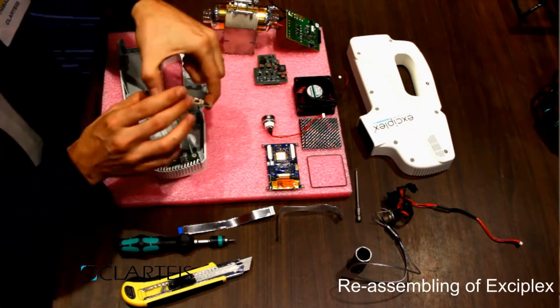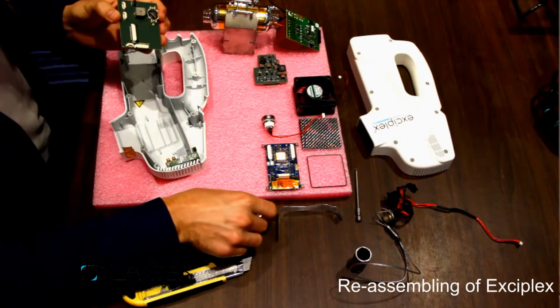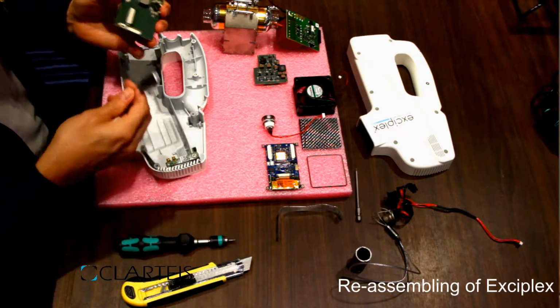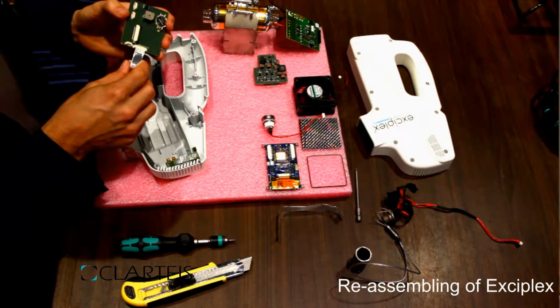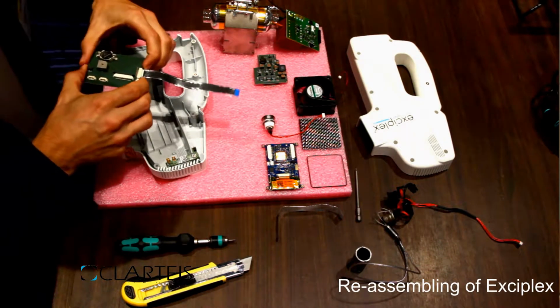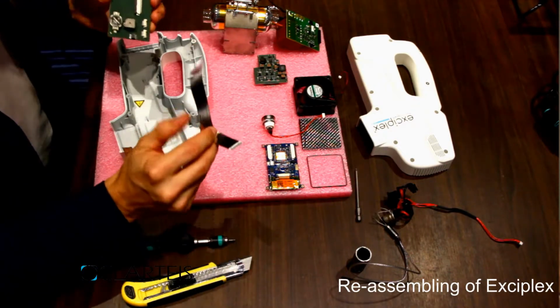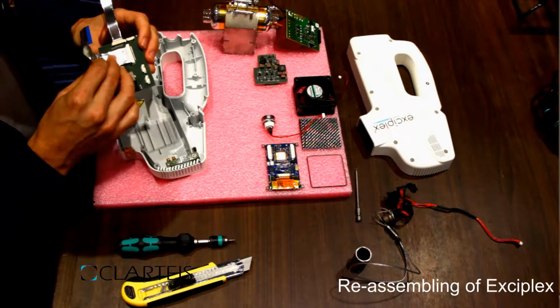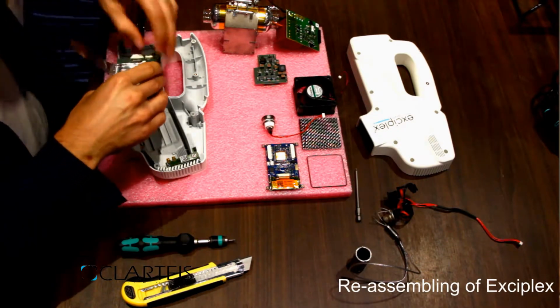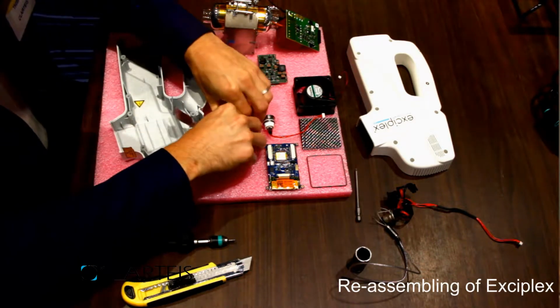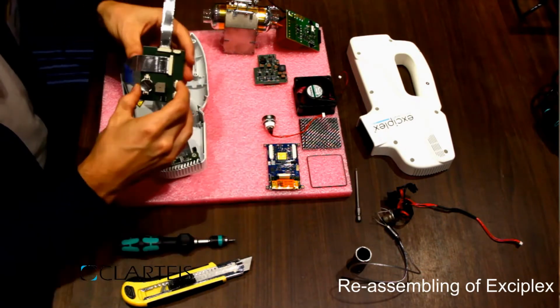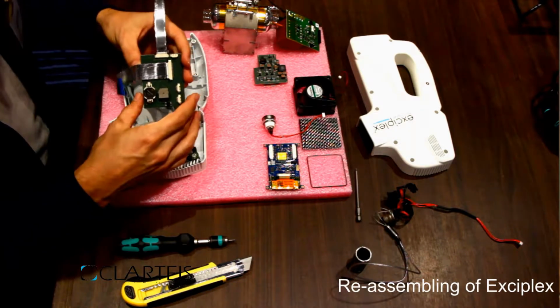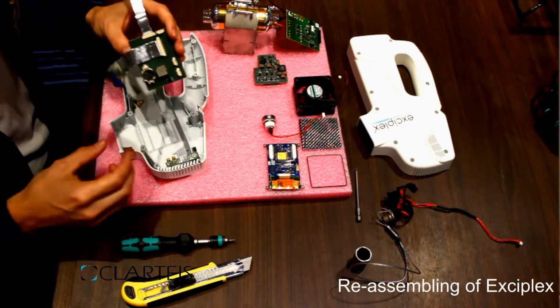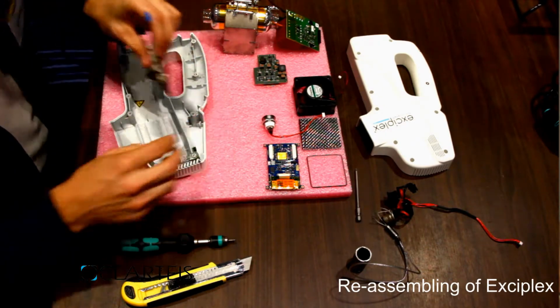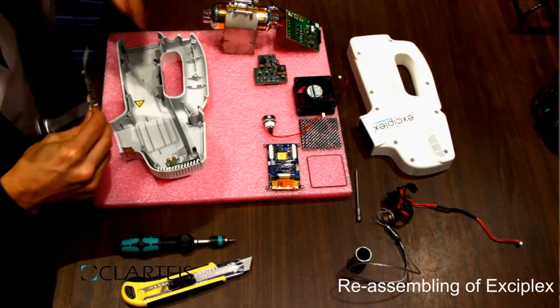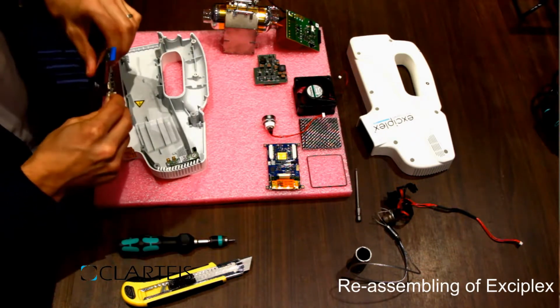Then take the low voltage board and connect the flat cable from the power board, the power flat cable, and also the display flat cable. Please remember that you need to lock the connector to make sure that the cable is well maintained. Now you can insert the LVB board inside the shell following the...